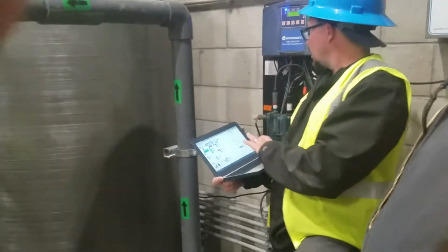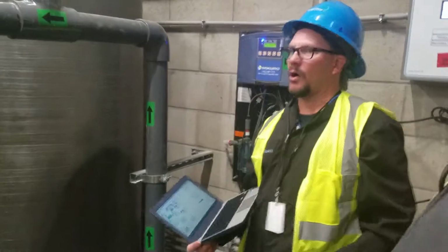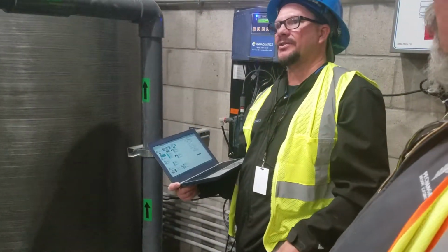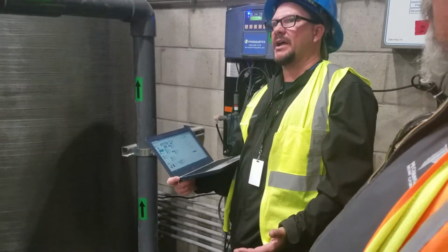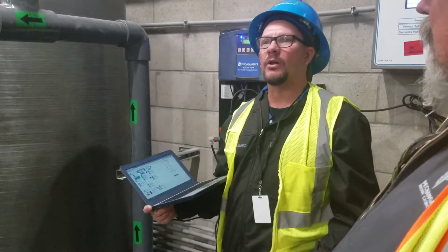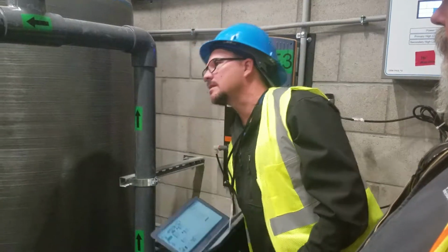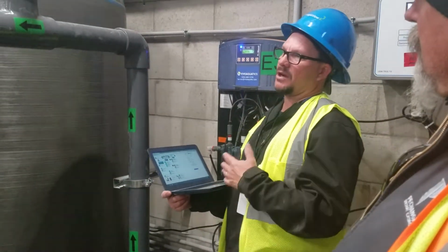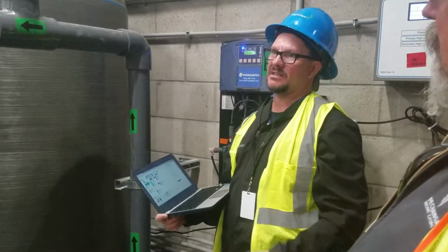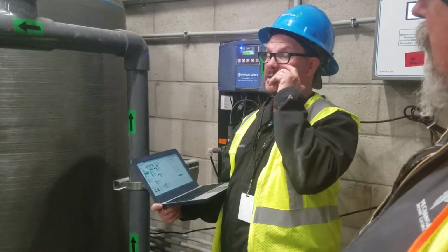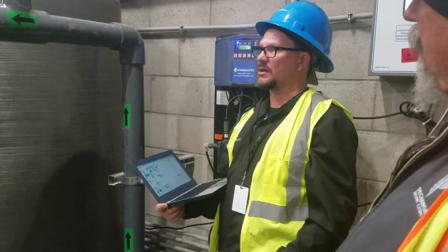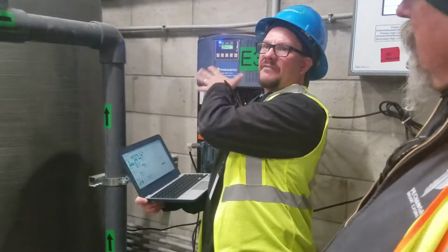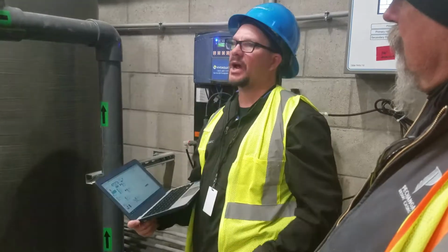So basically, the alarm is holding in there pretty good right now at 7.3. So, here's a little knowledge. Why is ideal 7.4 to 7.6? Bather comfort. The pH of your eyeball is 7.3, so we don't want to run set points at 7.3 and below for obvious reasons. Still neutral at 7.0, we're not going to hurt equipment, but it's all about bather comfort. So we can fine tune the pH around that, and that's what I've done here.